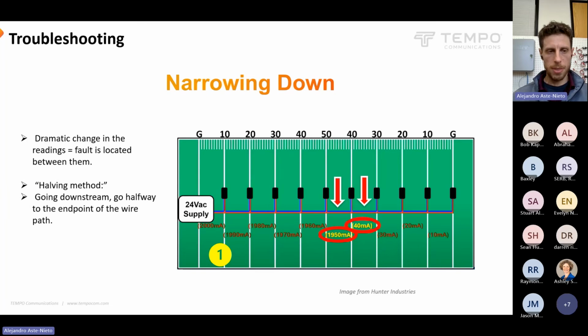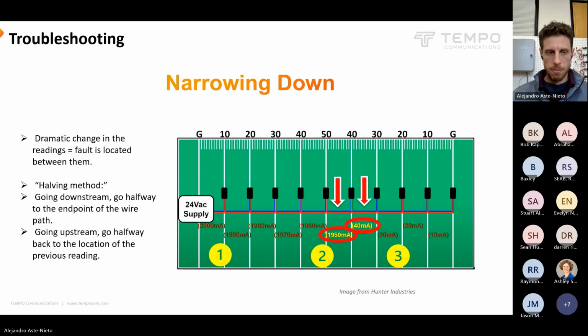halfway down the wire path and take a measurement. So we go halfway. We have a high number still, so we know we need to advance further to the right. So now we have a normal or a low number. We know we've passed where the change occurred. We go back halfway to our last previous measurement. And now we have the problem narrowed down between these two points where we measured high number, low number. The problem is in this valve box right here.